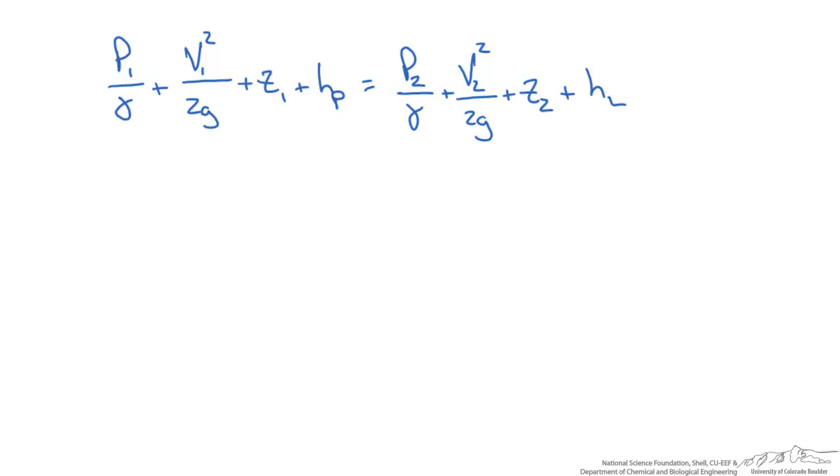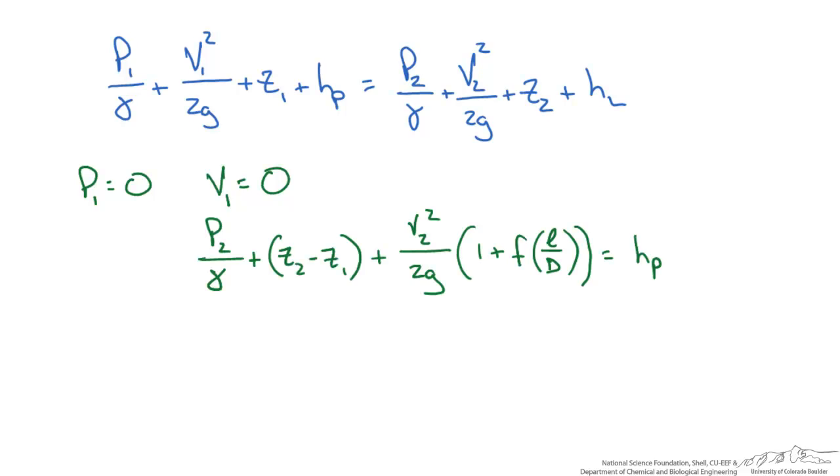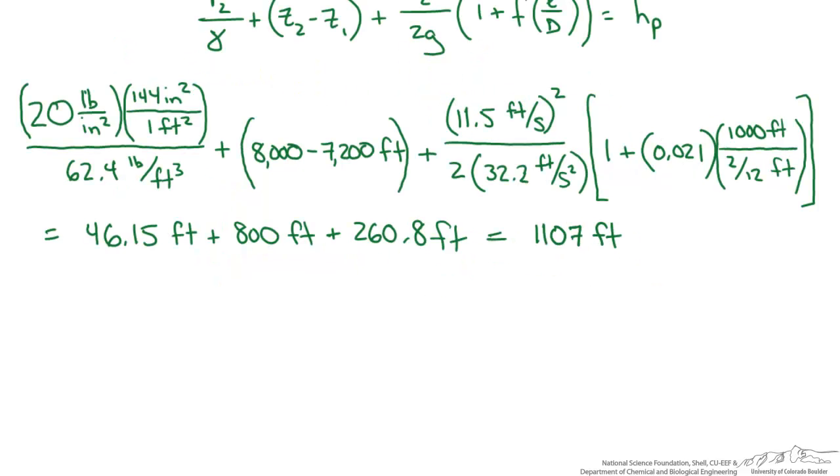Let's go back to our main equation and rewrite it in the form we're most interested in. We know if we use gauge pressure that P₁ equals 0 since it's open atmosphere. The velocity at point 1 is also 0, assuming the lake velocity is irrelevant. Knowing that, we could rewrite our equation, combining our head loss term with the kinetic term. At this point it's just plug and chug. When I plug in all these numbers I end up getting about 1,100 feet as our pump head.